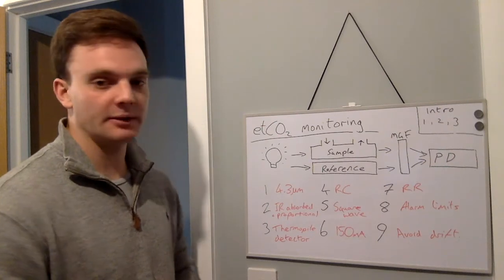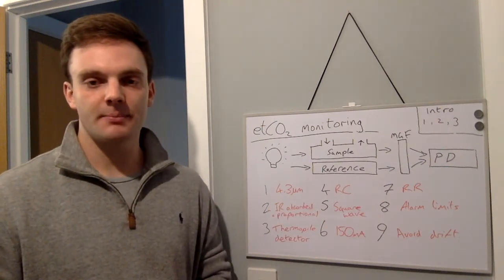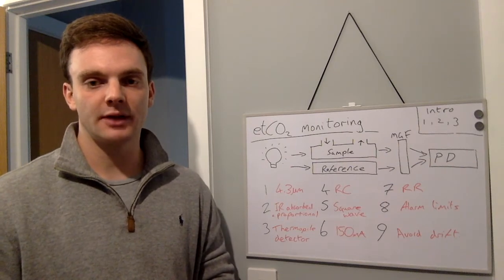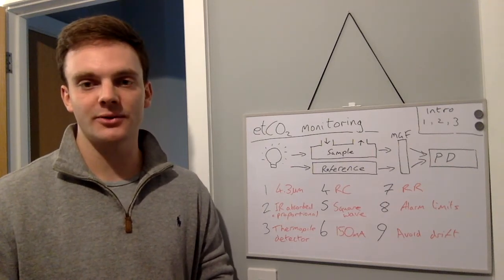We then have a reference chamber here, and the reference chamber is compared with the sample chamber in order to calculate a measurement for end tidal CO2.